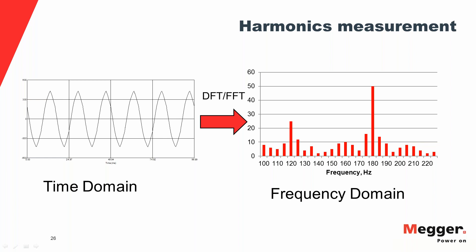When you analyze a waveform using DFT or FFT, you get different frequency components across a wide range of frequencies, each corresponding to a 5 Hz bin. For example, 180 Hz is at the center of a 5 Hz bin, with a 5 Hz bin to its right and left. Taking those three 5 Hz bins around 180 Hz gives a single 15 Hz band. All frequency components between 180 ± 7.5 Hz are grouped under the third harmonic. Similarly, frequency components within ± 7.5 Hz of 120 Hz are grouped under the second harmonic.